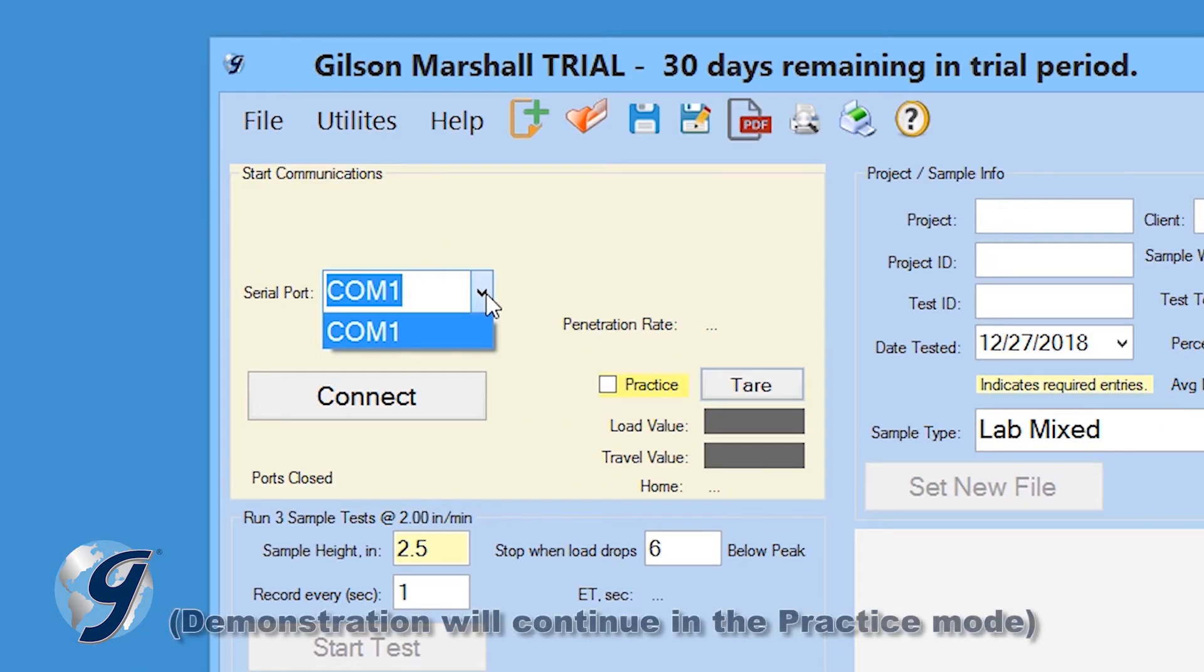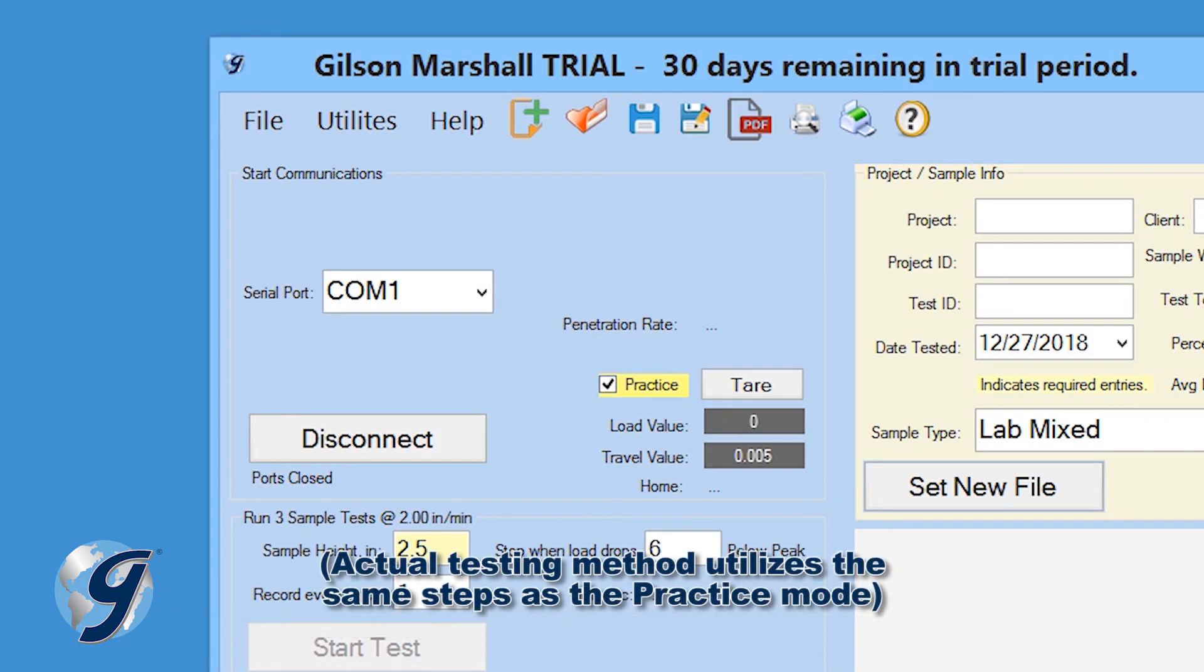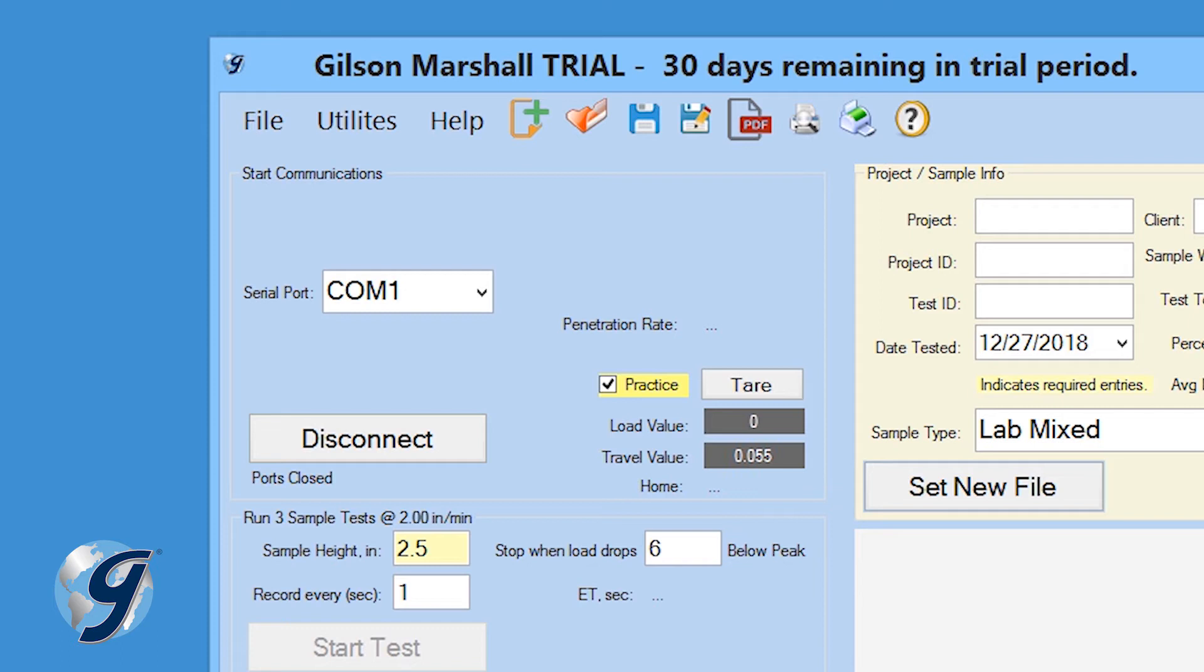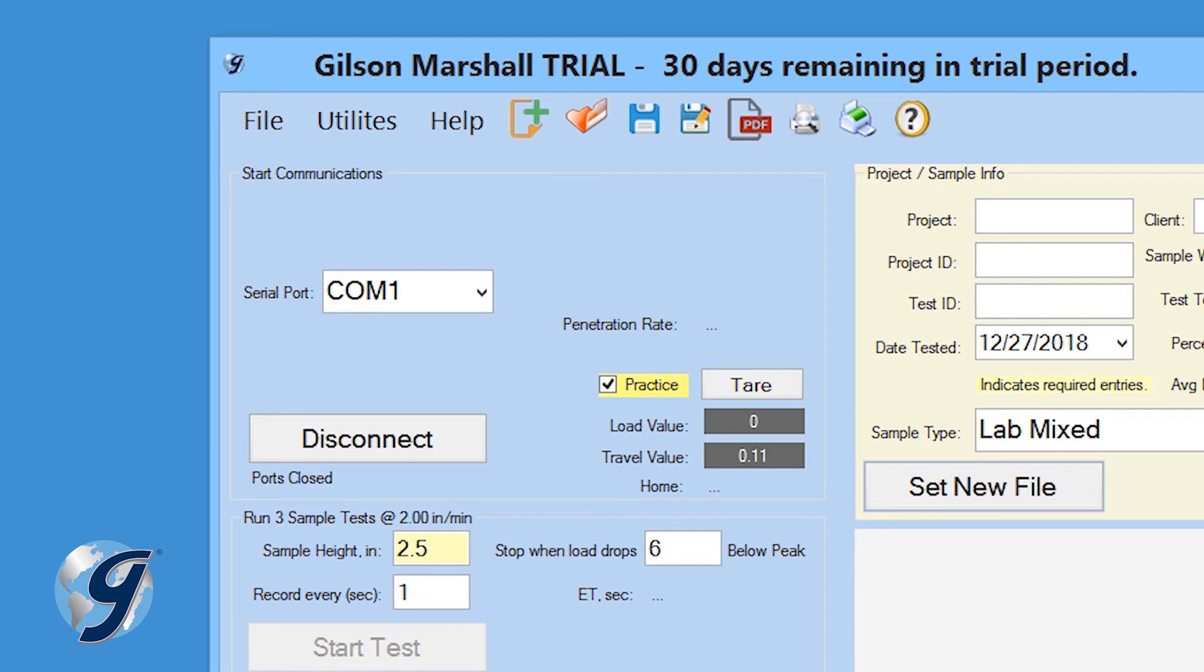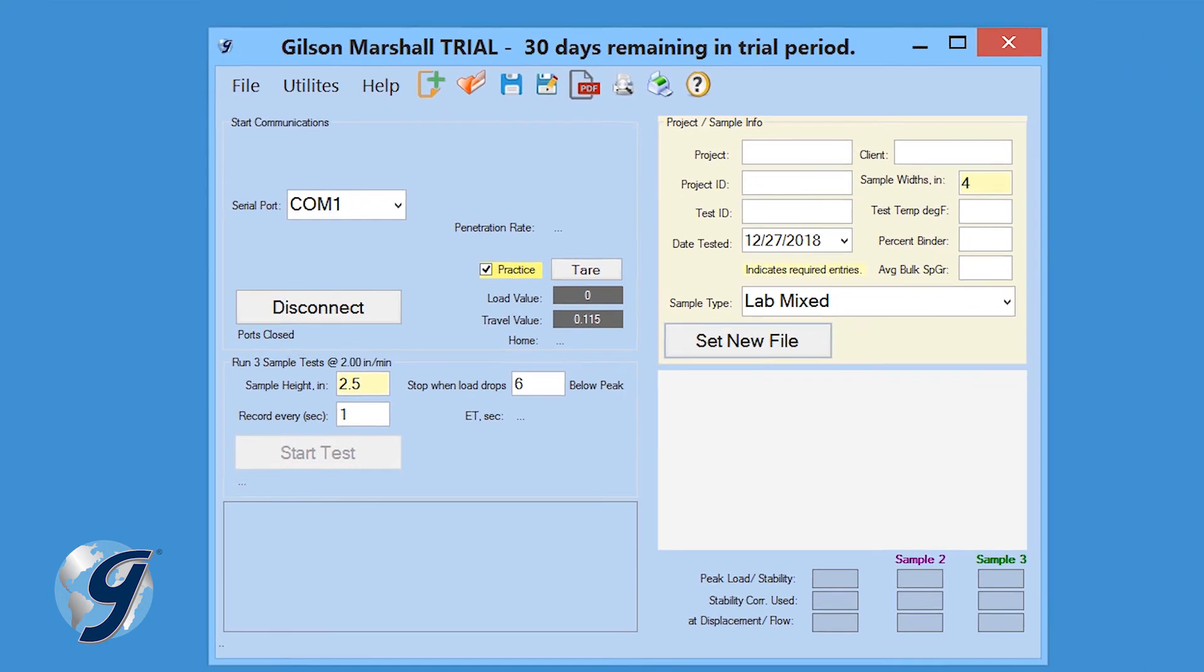Feel free to click on the practice box to familiarize yourself with the program and its operations. Uncheck the practice box once you are ready to continue with the test. Once connected, the load and travel values will be displayed in the bottom right corner of the Start Communications tile. Gently move the displacement transducer up and down to confirm the connection. The travel value should change.